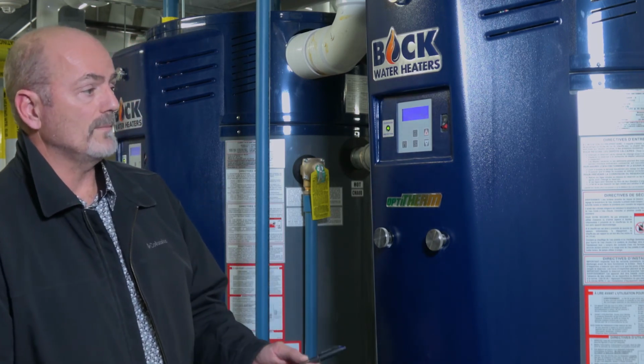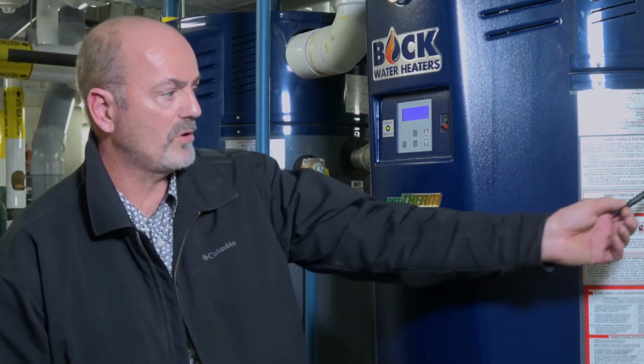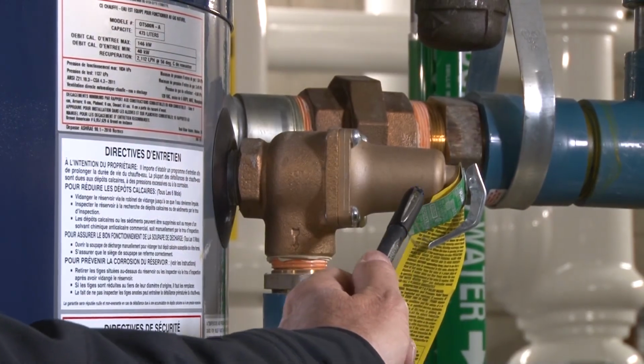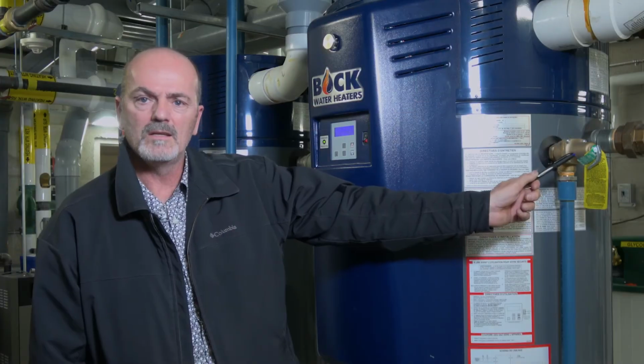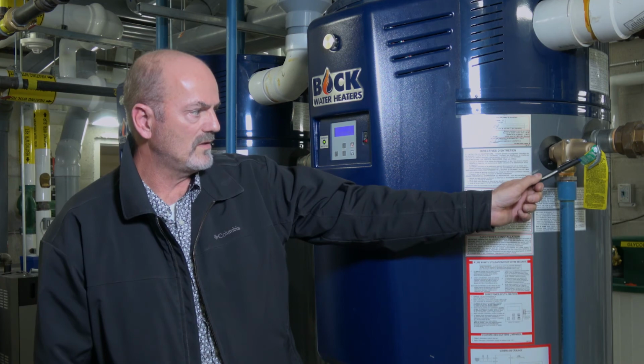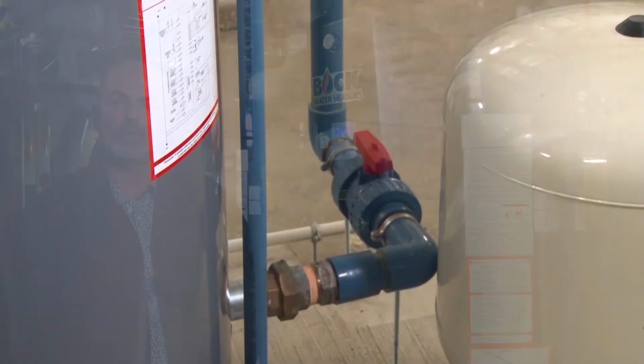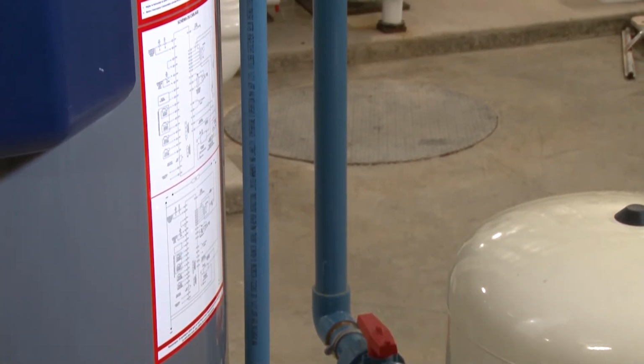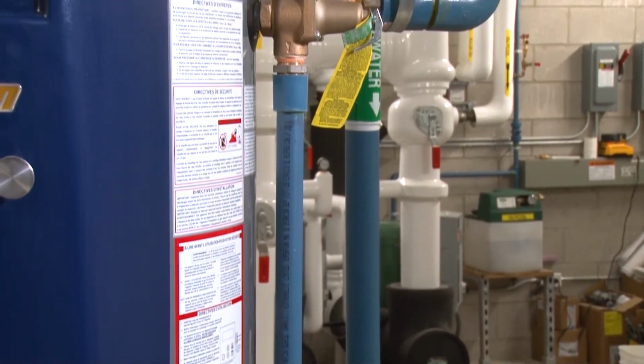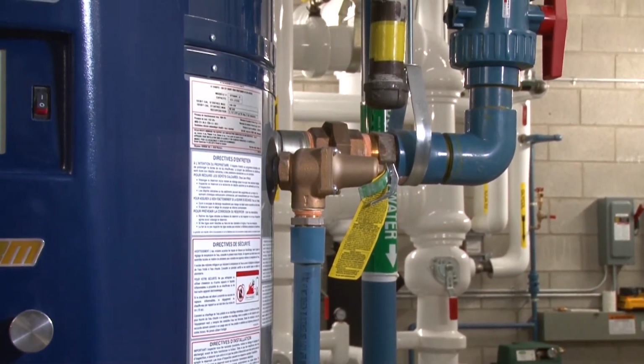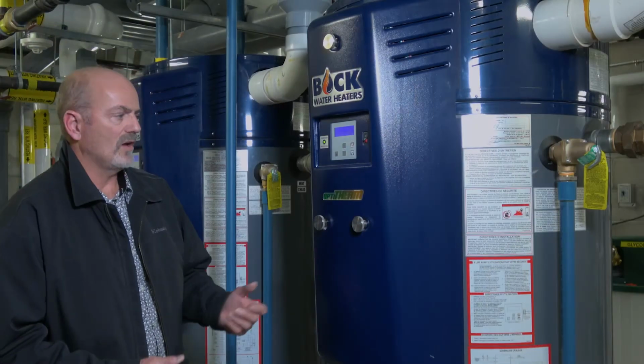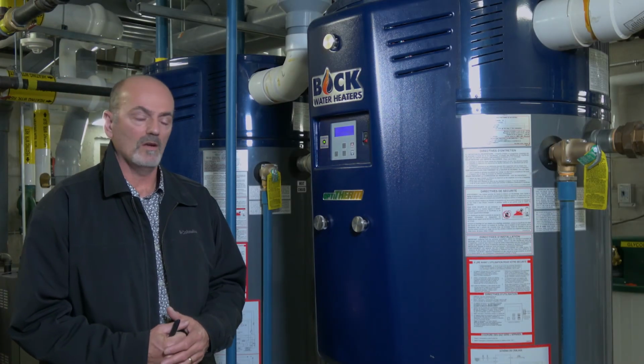Right. That's it. There is a pressure relief on this as well. If pressure goes above the rated PSI and/or temperature goes above the rated temperature, this will start to weep. It will blow off on the floor, and the next time maintenance comes in to look over everything, they will see that on the floor and know that there's a potential high temperature or high pressure issue with the heater.